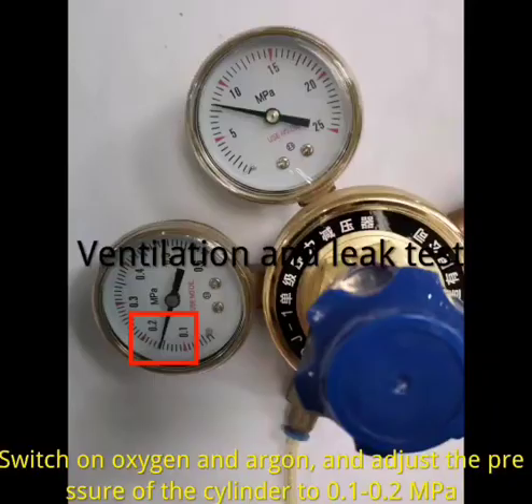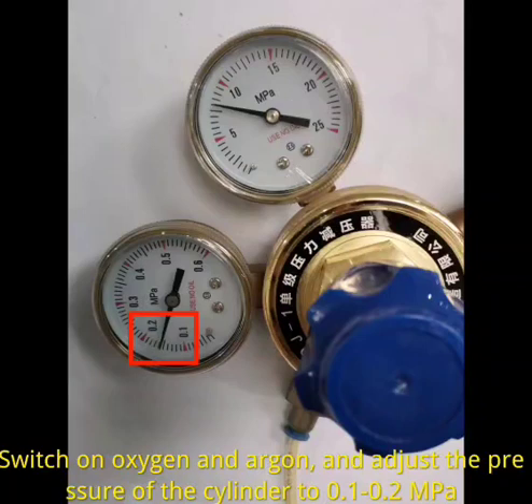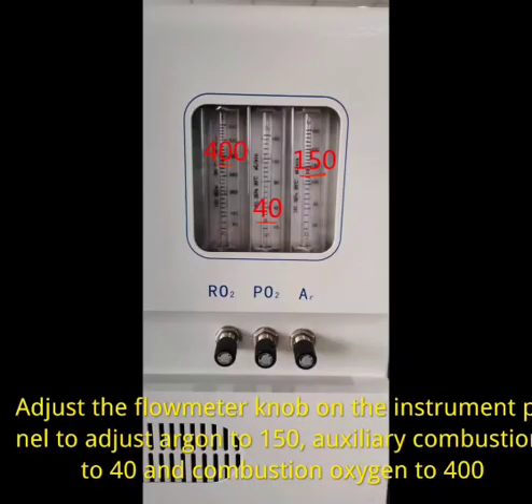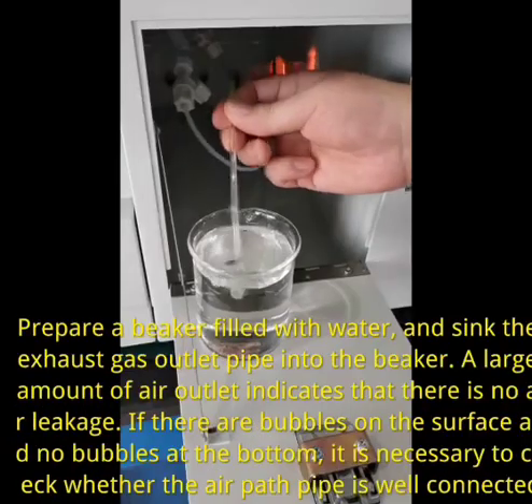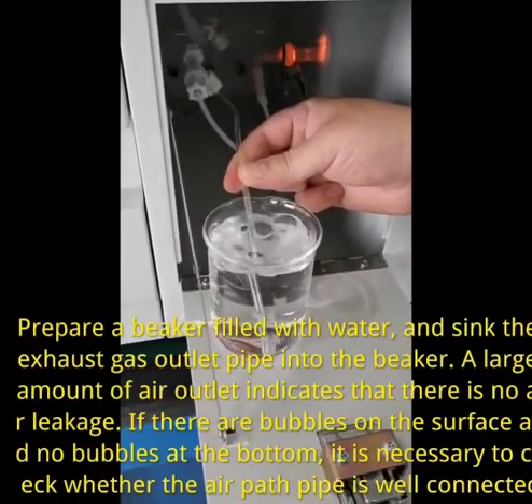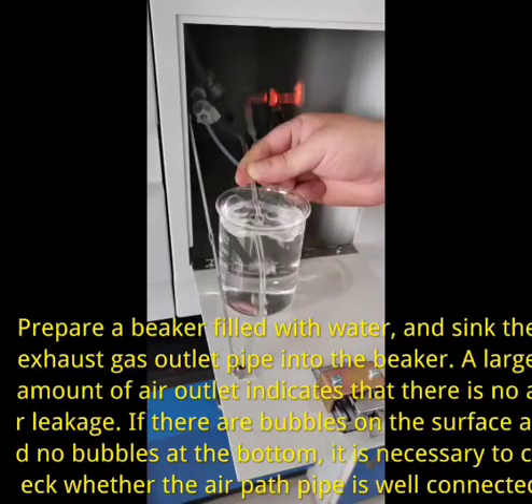Ventilation and leak test. Switch on oxygen and argon, and adjust the pressure of the cylinder to 0.1 to 0.2 MPa. Adjust the flowmeter knob on the instrument panel to adjust argon to 150, auxiliary combustion to 40 and combustion oxygen to 400. Prepare a beaker filled with water and sink the exhaust gas outlet pipe into the beaker. A large amount of air outlet indicates that there is no air leakage. If there are bubbles on the surface and no bubbles at the bottom, it is necessary to check whether the air path pipe is well connected.